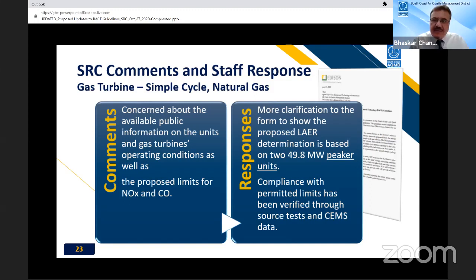That's exactly the reason why we include ammonia testing, typically annual, just to make sure the ammonia slip isn't increasing, because as the catalyst gets older you lose some activity. We want to maintain those limits, 2.5 ppm NOx and 5 ppm ammonia. NOx is continuously measured and ammonia is tested yearly. Hopefully that'll change soon once we have the ammonia CEMS certification in place, so we can have continuous ammonia monitoring too.